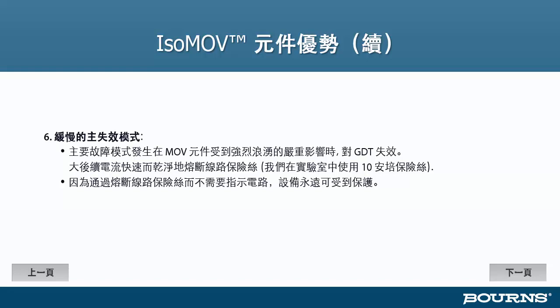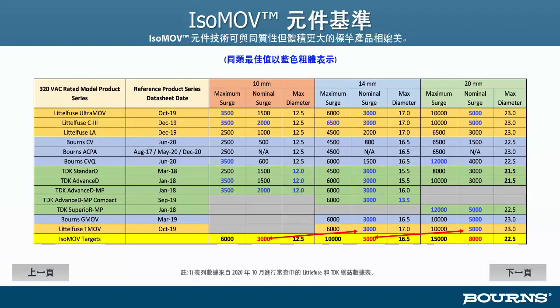There are competitive products out in the field that indicate when the MOV has gone offline due to overheating, so that the maintenance people can come out and replace it. That's not a concern here, because the high leakage failure mode of the MOV, which slowly heats up and activates the thermal disconnect, simply doesn't exist in the IsoMOV component. In an IsoMOV protector typical failure mode, the device suddenly experiences a short and blows the line fuse. So the indication of the failure is the fact that the equipment is no longer working because it has been safely taken offline. So how do we stack up against the competition?